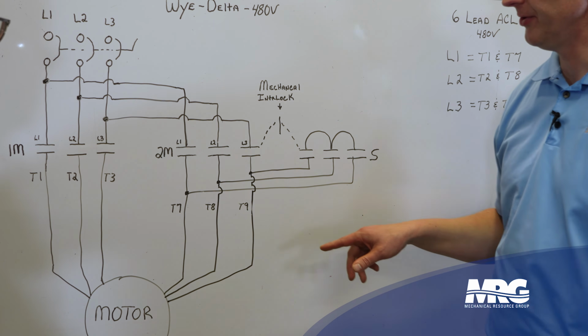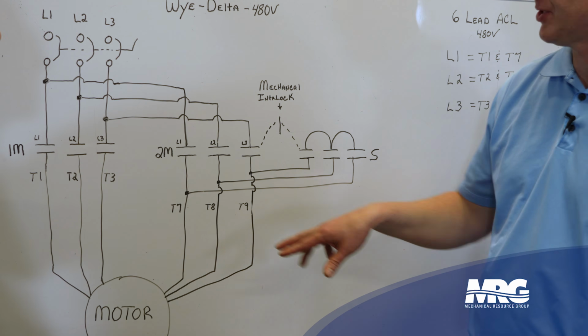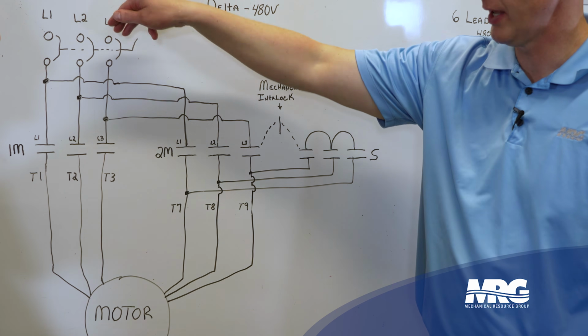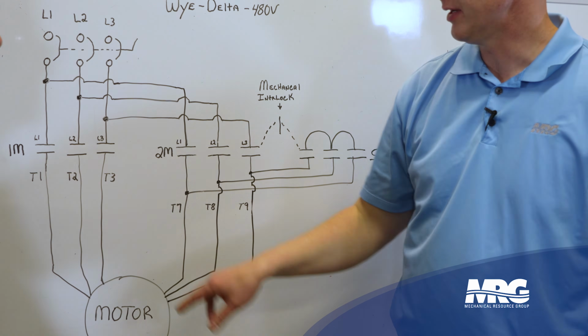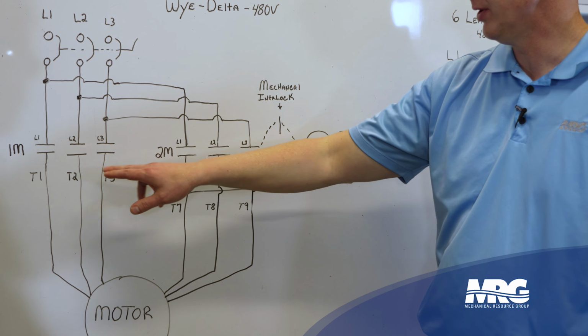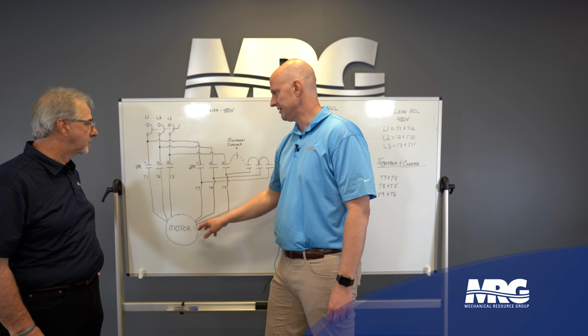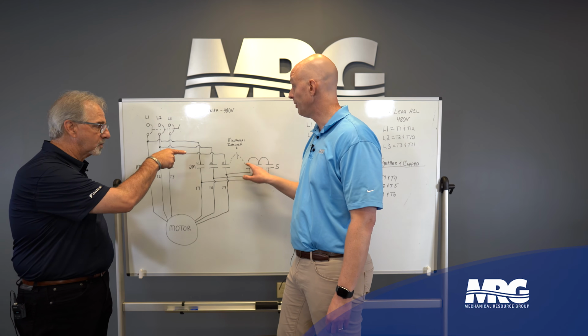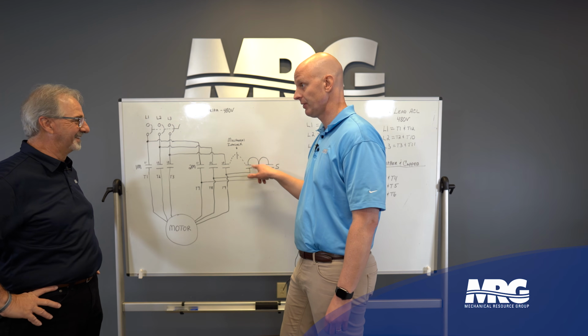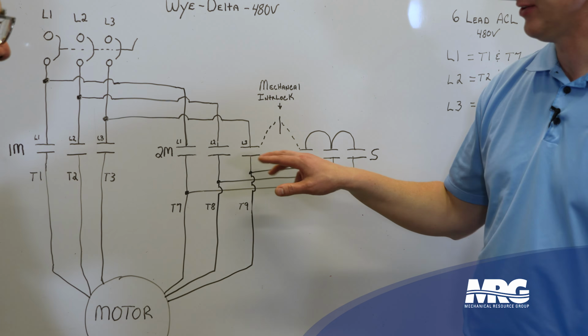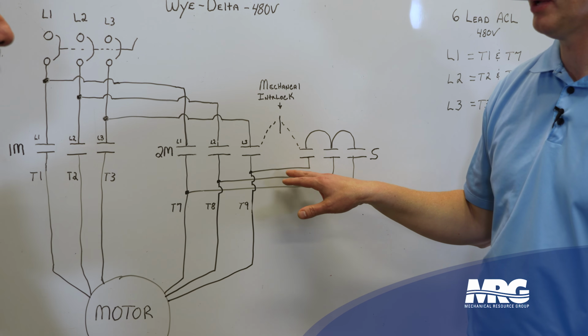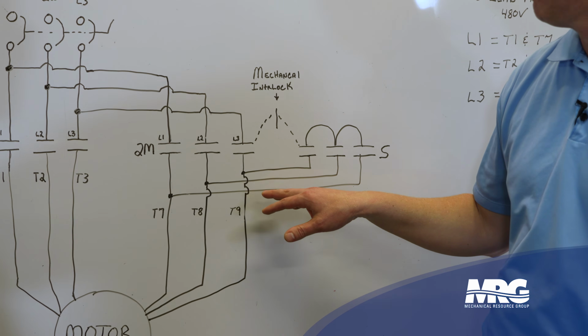Jeff, let me walk through this again with you, just make sure I got this thing straight. So here's our supply. We got the M1 contactor. We got T1, 2, 3. We're going to energize this and get the motor spinning. Right, but we have to short the Delta. Right, yeah. We got to short that Delta. Yep. It's really a false Delta. It's not truly faulting or shorting the motor.